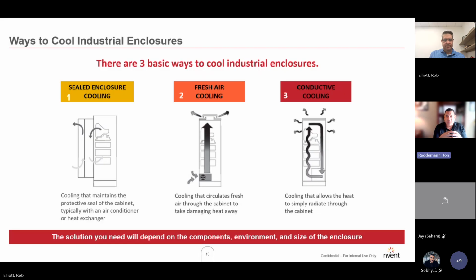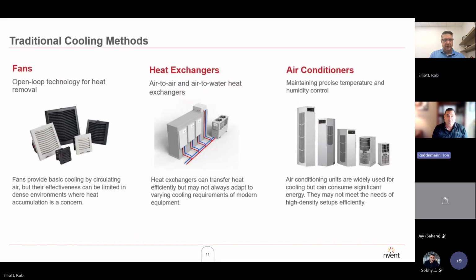An air conditioner is an electromechanical device, so we're limited in our life cycles. Every time we start and we stop, we're going through a life cycle. So, if we have an air conditioner that's 2 to 3 times larger than needed, it will cycle 2 to 3 times more frequently. Therefore, it will fail that much more frequently. Okay. Right. So, thank you.